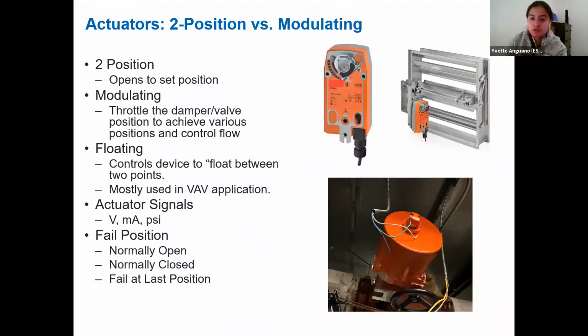So you'd want to see your damper be closed at a 2-volt signal, and then, as an example for an outdoor air damper, you'd want it to be at minimum OA at a 6-volt signal, and then it would be fully open at a 10-volt signal. And then a last thing to consider for actuators is setting a fail position. So you can set your actuator to fail in a certain position when there's a loss of power. And so you'd provide that actuator with a spring return so that in the loss of power condition, the actuator would fail your damper or valve in a certain position, whether it's open or closed.